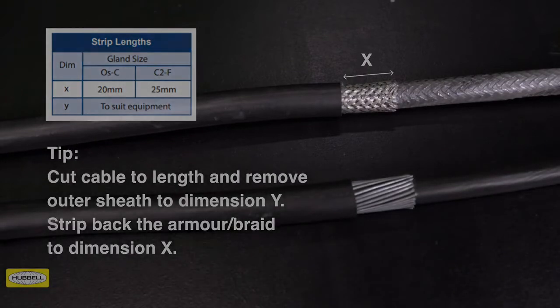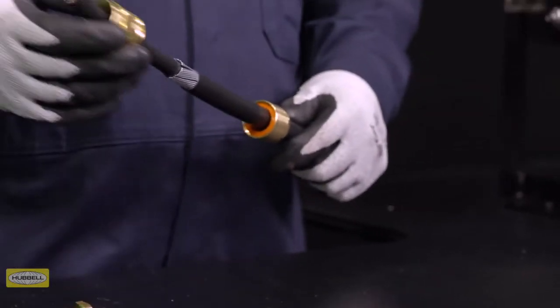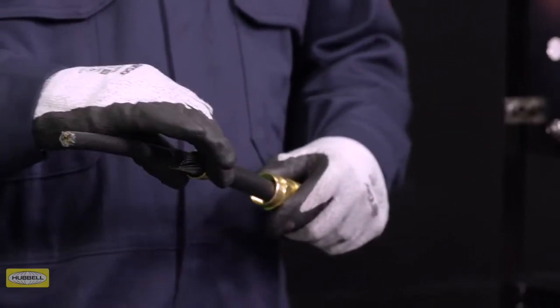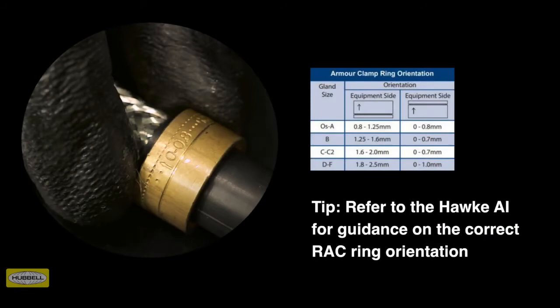Slide the back nut, middle nut, and armor clamping ring onto the cable. Ensure that the orientation of the reversible armor clamping ring is correct, with the arrowhead indicating the correct armor, braid, or tape pointing to the equipment. Always refer to the Hawke assembly instructions for guidance on the correct armor clamping ring orientation. Tip: alternative rings may be required if the cable does not fall within the RAC standard clamping range.